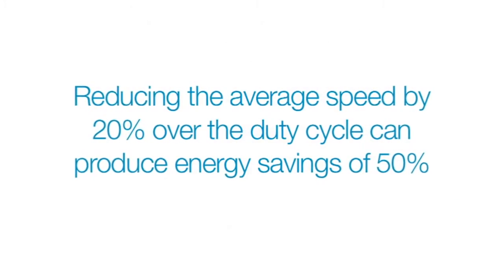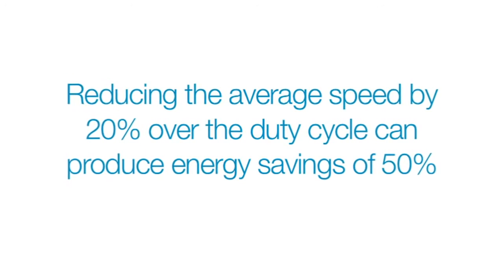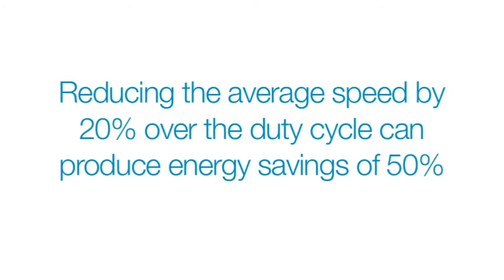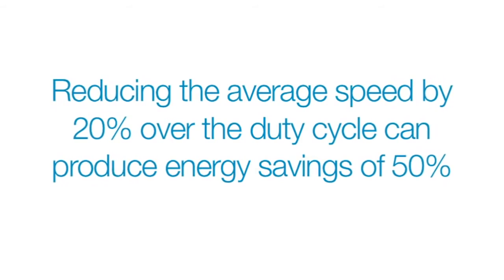The nature of VFDs is that they enable variable speed. If you're converting your fan from fixed to variable speed and reduce the average speed by only 20% over the duty cycle, you can expect energy savings of 50%. The savings can be even greater depending upon your application and duty cycle.